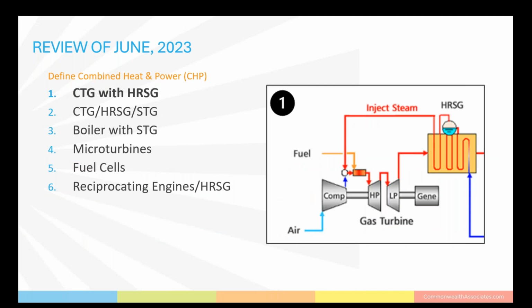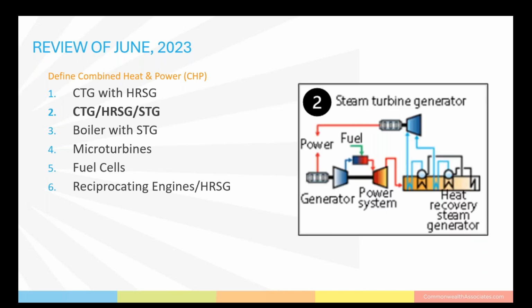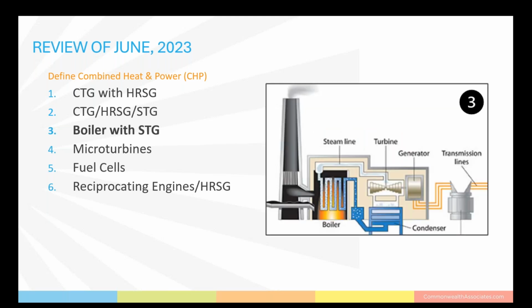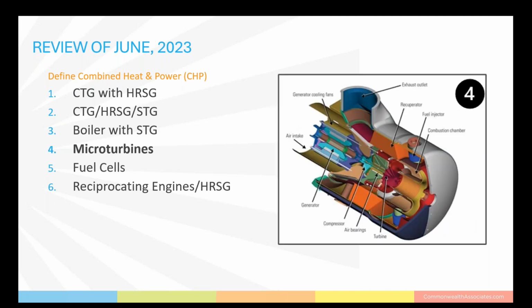There are a few types of CHPs to consider for your application. First is a combustion turbine generator with a heat recovery steam generator. The HRSG captures the CTG exhaust and uses that exhaust to heat water. Second is adding a steam turbine generator to the first option. By adding the STG to the process, it can extract energy from the pressurized steam produced in the HRSG to create a second source of power. Third is a boiler with STG option, similar to the first option, except that the boiler is used for the heating process instead of the HRSG. The boiler gets heat energy from the burning process of fuels such as coal or biomass.